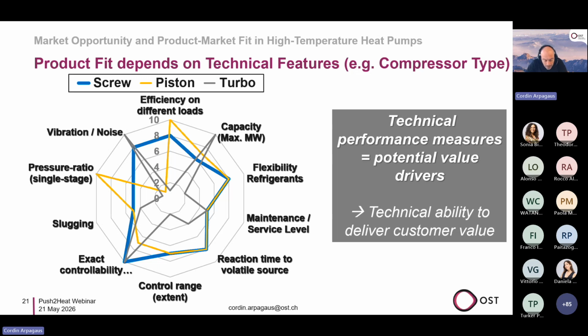And for a heat pump, which is driven by a compressor, the compressor technology is very much deciding on that. And here we did discussions and workshops and tried to come up with a spider diagram for different compressor technologies. So we have different criteria to judge, let's say, which compressor technology fits better in what conditions. For example, screw compressors are flexible in refrigerants, for example. Reaction time to volatile sources is high, and so on.